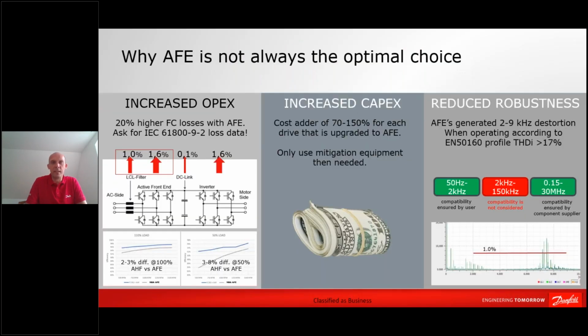I'll put in an example here for you, and that's why I sometimes am a bit afraid of the standard in the market. And now I also heard 28 of you have a preference for active front-end drives. And active front-end drives is a fairly good technology. We also offer active front-end drives at Danfoss, but it's not always the best solution for harmonic mitigation. There are three main reasons for that.